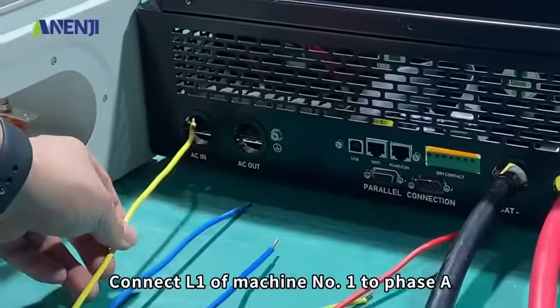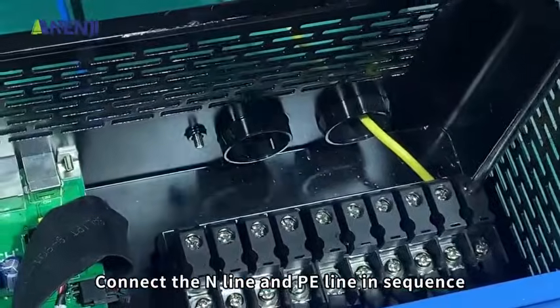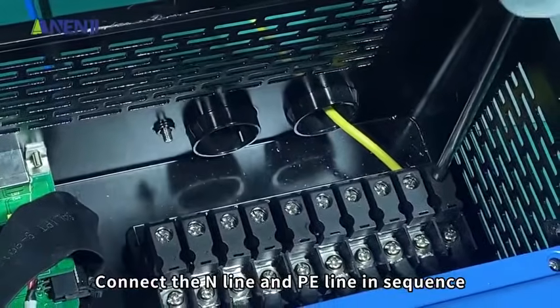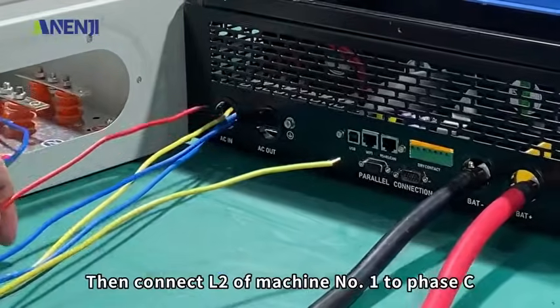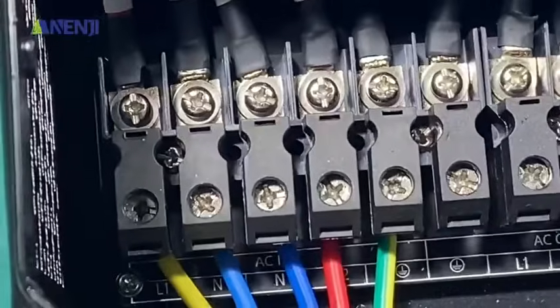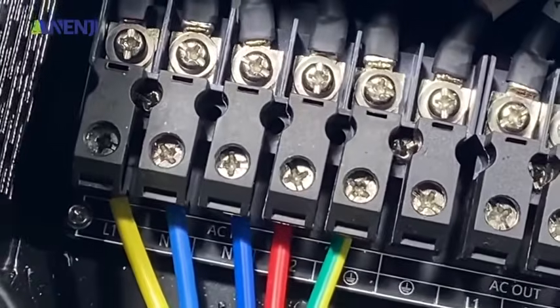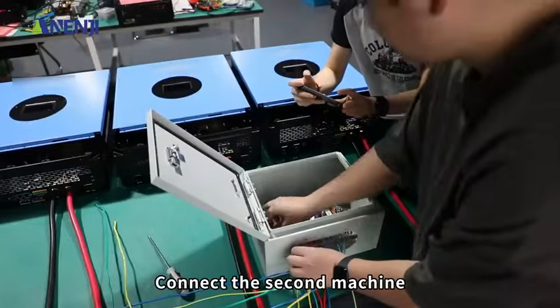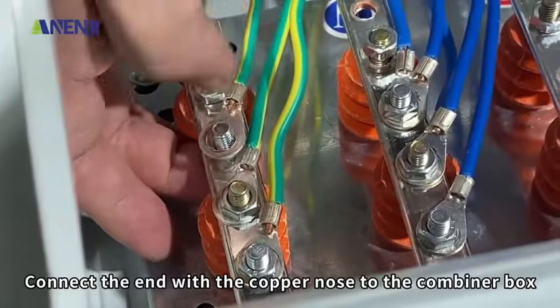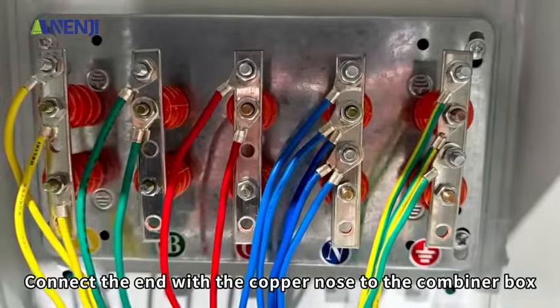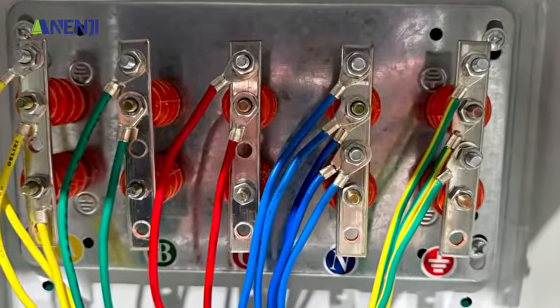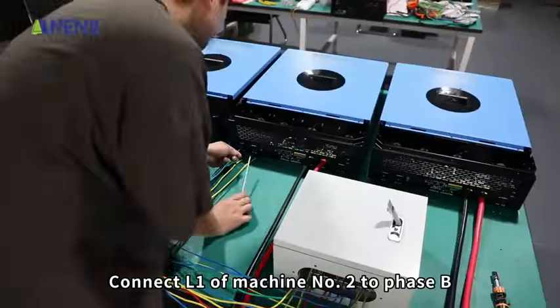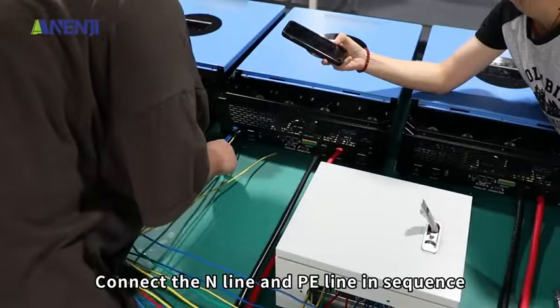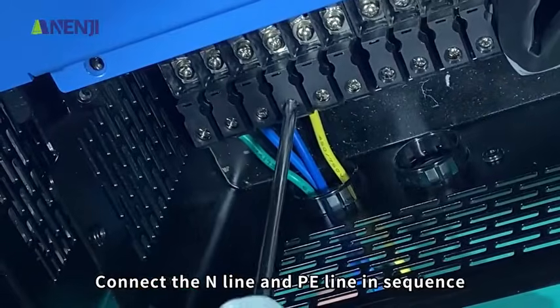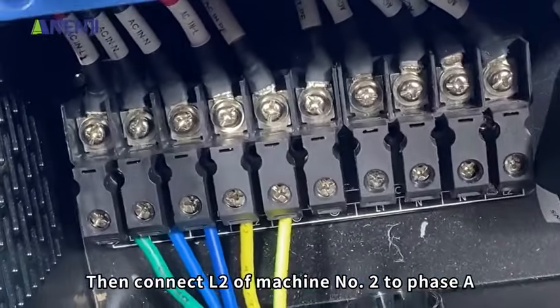First, connect L1 of machine number 1 to phase A. Connect the N line and PE line in sequence. Then connect L2 of machine number 1 to phase C. Connect the second machine. Connect the end with the copper nose to the combiner box. Connect L1 of machine number 2 to phase B. Connect the N line and PE line in sequence. Then connect L2 of machine number 2 to phase A.